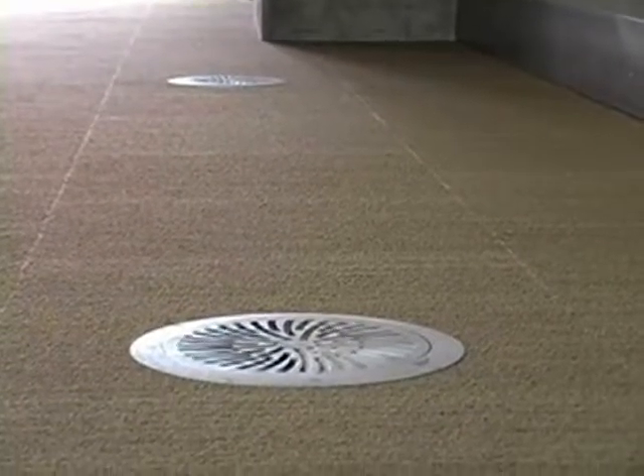We're back inside the building now, and I see these vents popping up through the floor. What's going on here? Well, Nick, this is a different type of air conditioning system for a commercial building, called UFAD, or underfloor air delivery system.